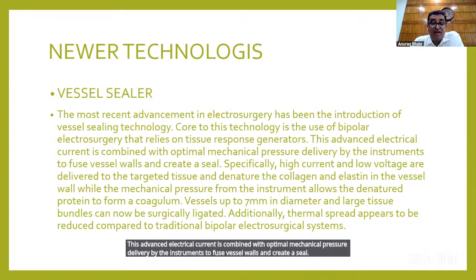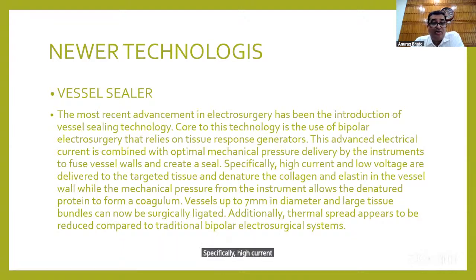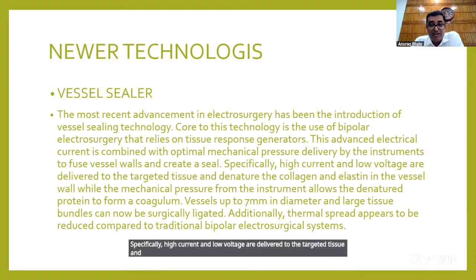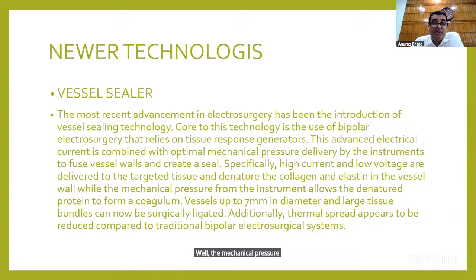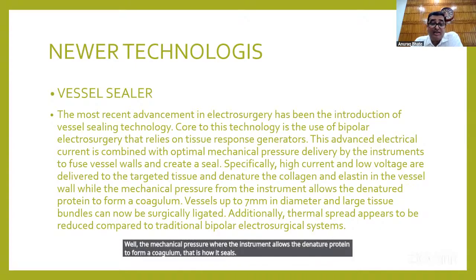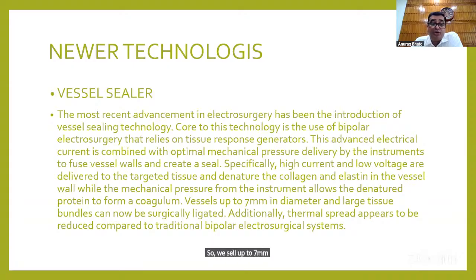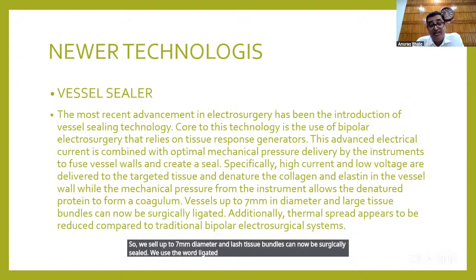Specifically, high current and low voltage are delivered to the targeted tissue and denature the collagen and elastin in the vessel wall, while the mechanical pressure from the instrument allows the denatured protein to form a coagulum. That is how it seals. So vessels up to 7 millimeter diameter and large tissue bundles can now be surgically sealed. We use the word ligated, but it is surgically sealed.